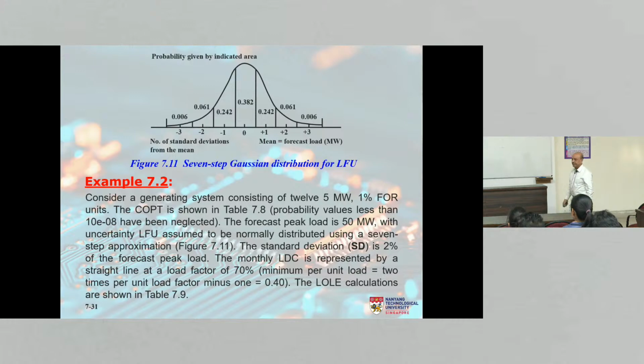So I go back to an example to illustrate, which is always good for all of us to understand. Consider a generating system comprising 12 units of 5 megawatts each with 1% forced outage rate. You notice that most of my examples use identical units. Why? Because hand calculations are easier. You can use binomial. That's the reason. If I don't give you identical units, then you have to use the algorithm. Remember?